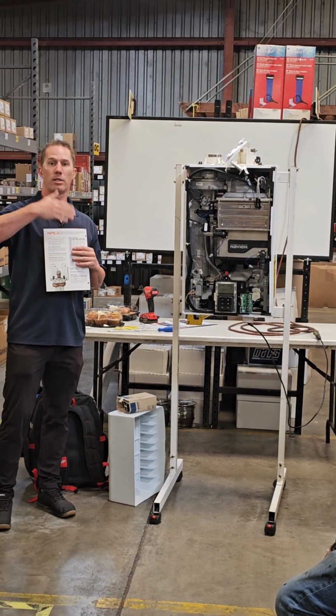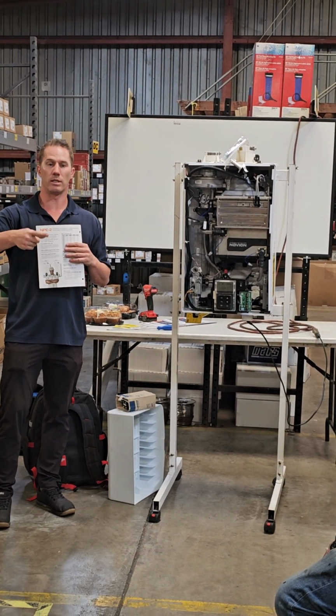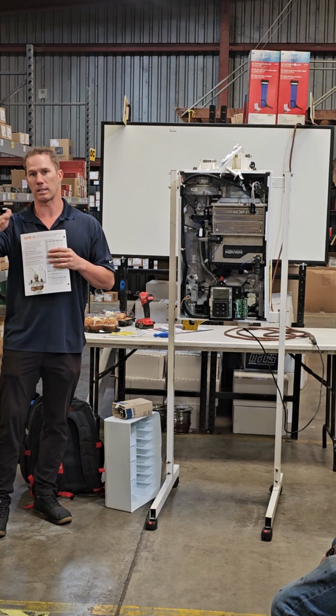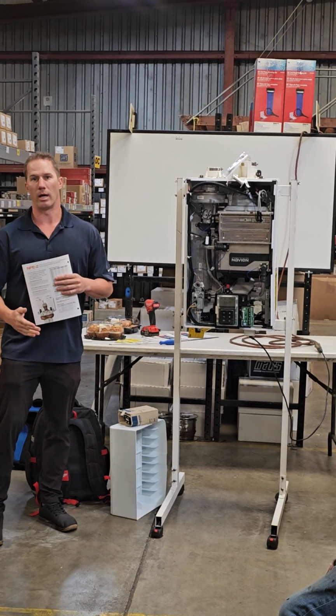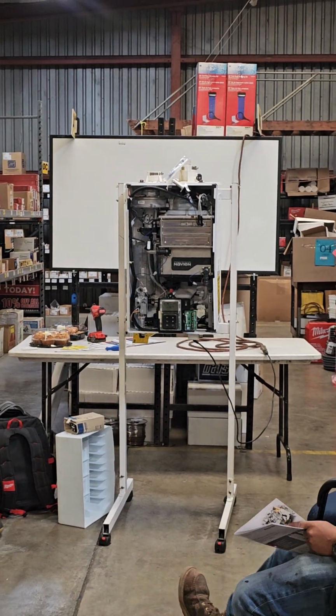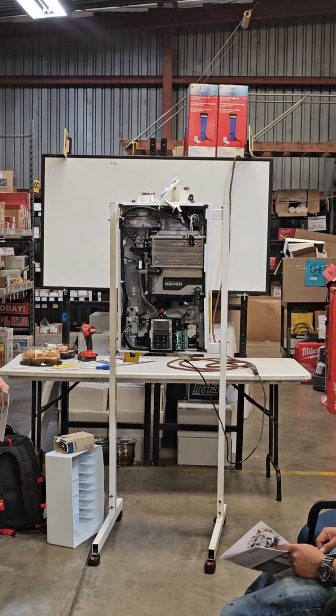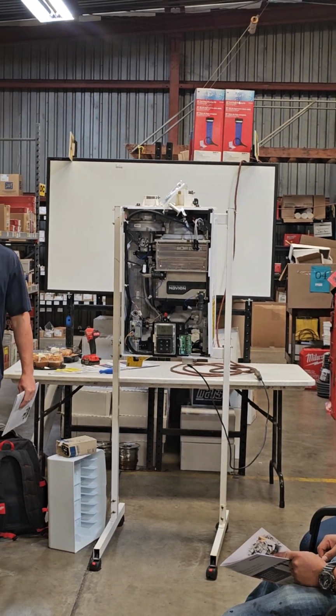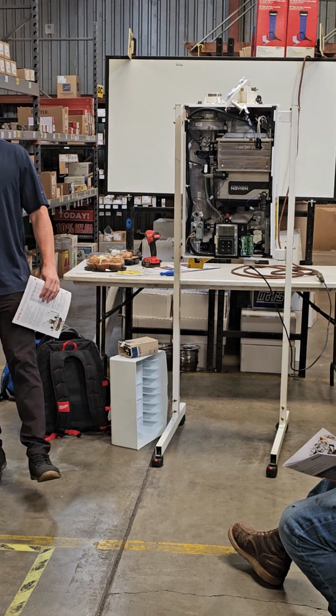So 3 turn on and start reading the GPMs. If it's a lower GPM demand, it scales back to just 1 unit. Is that kind of what you're asking? Or can you stage them by temperature, like setting some at 120 and some at a different temperature? No, if you're going to do that, you're not cascading them together.